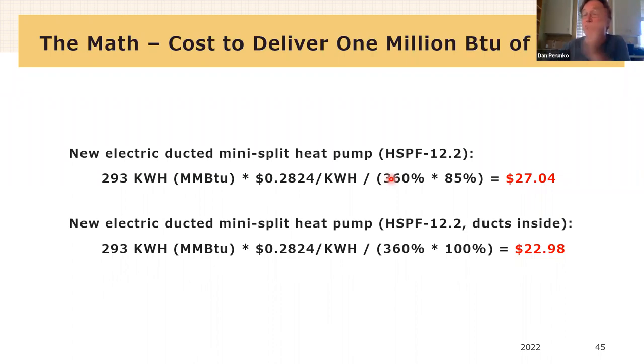When the heat pump is heating and it's really, really cold outside, its COP goes down to like 1.5 to 2. And if it's heating on a mild day where there's tons of ambient heat outside, it goes up to like 5, right? So you have this range of potential efficiencies. This 3.6, or 360%, is a pretty fair multiplier. And these are good ducts, right? You don't want to do bad ducts. So when you do the heat pump for 1 million BTUs, the metric for energy is now kilowatt hours instead of therms of gas. Pardon me, 293 kilowatt hours is equal to 1 million BTUs.